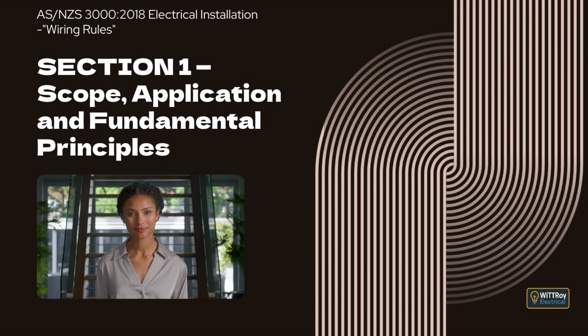Clause 1.5.4.5 Protection by obstacles. Obstacles are used only where access is restricted to competent persons or people under supervision of a competent person. Obstacles can prevent accidental contact with live parts, but they are not intended to stop intentional contact. Examples are mesh guards, rails, or screens that block casual access. Obstacles may be removable without a key or tool, but they must be secured so they cannot be accidentally displaced.